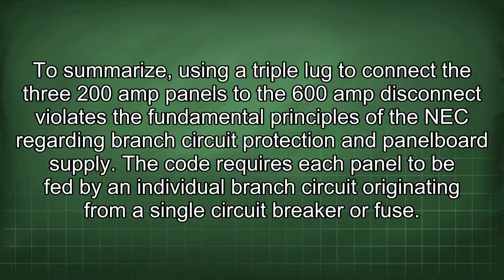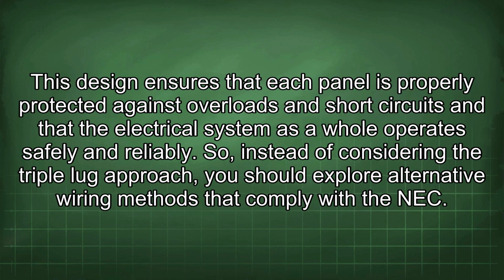To summarize, using a triple lug to connect the 3 200 amp panels to the 600 amp disconnect violates the fundamental principles of the NEC regarding branch circuit protection and panel board supply. The code requires each panel to be fed by an individual branch circuit originating from a single circuit breaker or fuse. This design ensures that each panel is properly protected against overloads and short circuits and that the electrical system as a whole operates safely and reliably.